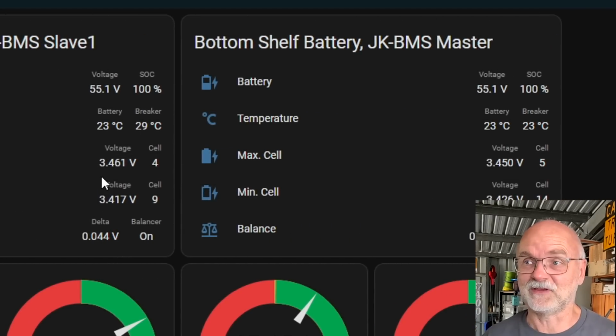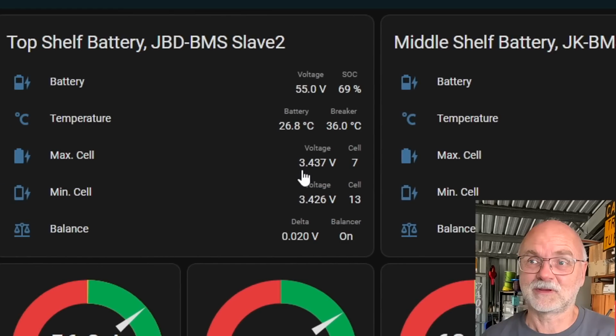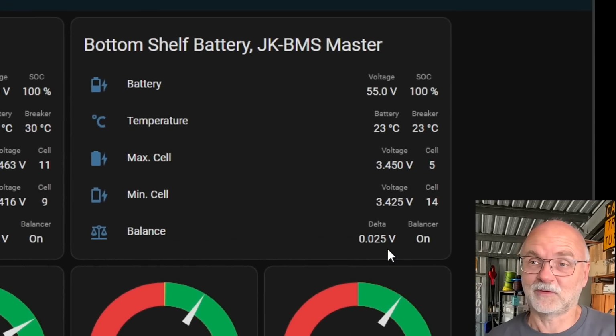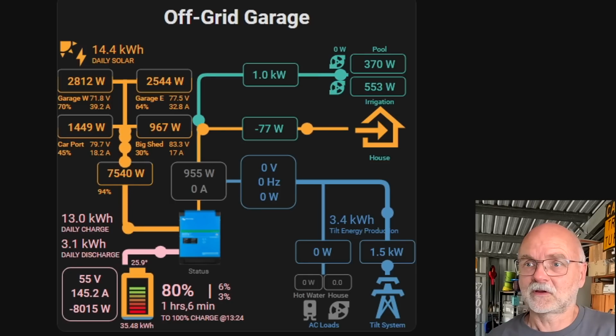But we can also see that the maximum cell voltage in the middle shelf battery is at 3.47 volts, 3.45 volts in the bottom shelf, and 3.44 volts in the top shelf. So the balancers are actually already on in all three BMSs. Deviation is 20 millivolt, 50 millivolt, and 25 millivolt. We're having a quick look here.